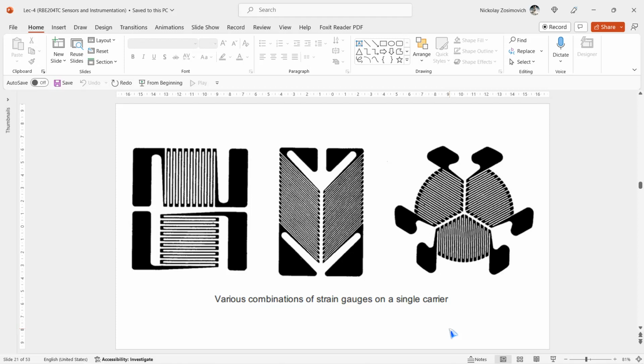The way out is modulation. The bridge circuit supply voltage is not a DC, but an AC voltage with fixed amplitude and frequency. In this case, the output is an amplitude-modulated signal with suppressed carrier, which can be amplified without difficulty. Offset or low-frequency noise from the amplifier may be removed by a simple high-pass filter. We will discuss this a bit later when we study uncertainty. Demodulation by synchronous detection will yield the original amplified signal, and using this method, strain down to 0.01 microstrain can be measured very easily.